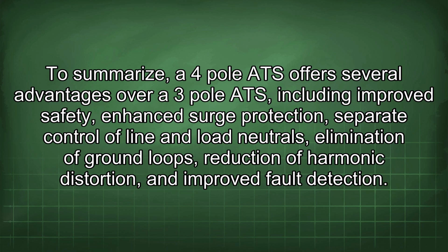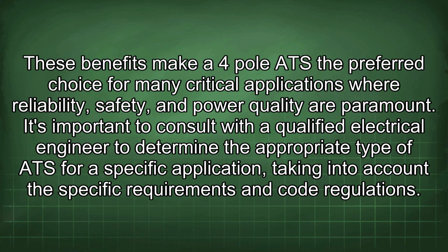To summarize, a 4-pole ATS offers several advantages over a 3-pole ATS, including improved safety, enhanced surge protection, separate control of line and load neutrals, elimination of ground loops, reduction of harmonic distortion, and improved fault detection. These benefits make a 4-pole ATS the preferred choice for many critical applications where reliability, safety, and power quality are paramount. It's important to consult with a qualified electrical engineer to determine the appropriate type of ATS for a specific application, taking into account the specific requirements and code regulations.